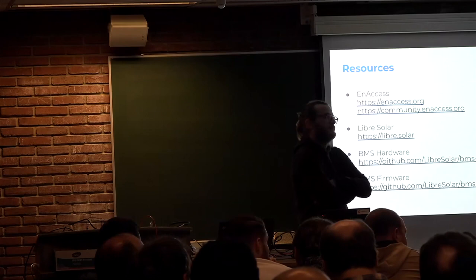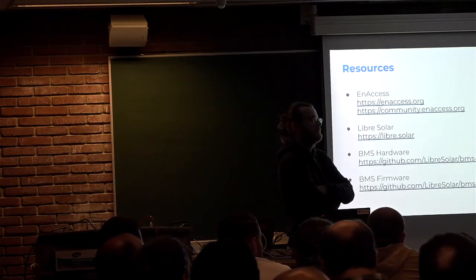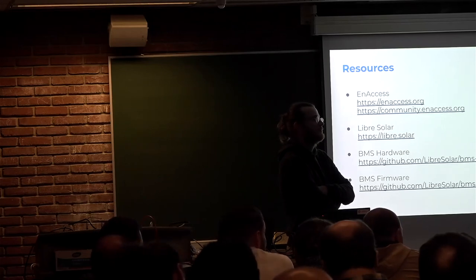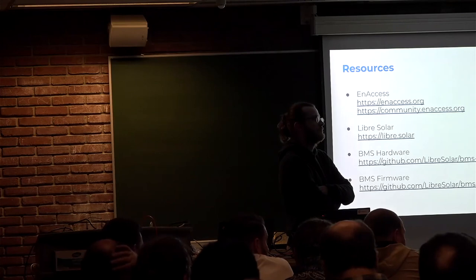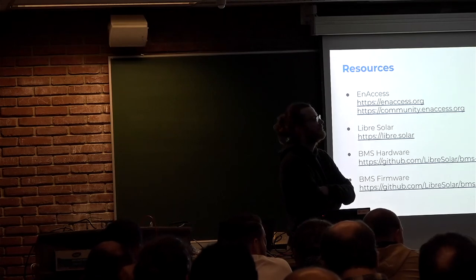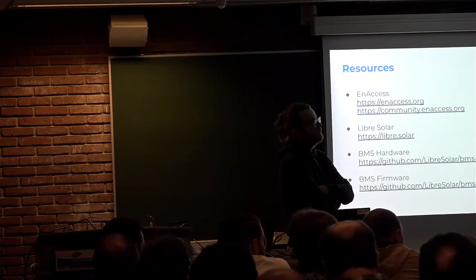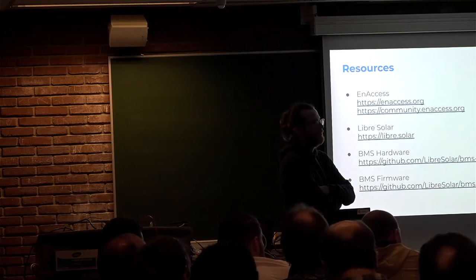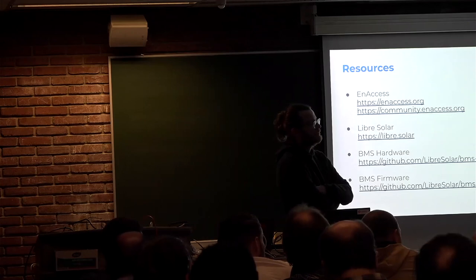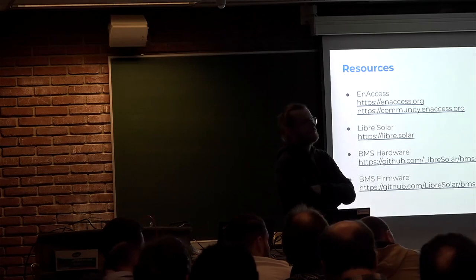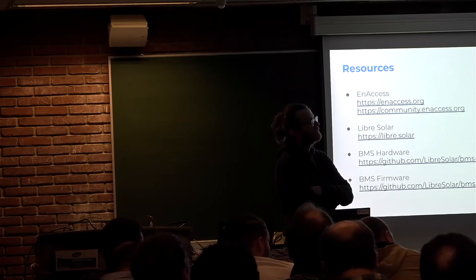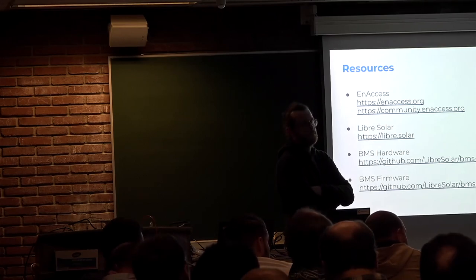Have you had cases where you needed to handle balancing between lithium cell storage and other kinds of storage, such as compressed air, concrete, or redox flow batteries? So far it has only been lithium cells of different chemistries — lithium iron phosphate and lithium nickel manganese cobalt oxide. We were in discussions with people developing redox flow batteries, where the voltage is smaller, so you could potentially monitor multiple cells at once and get an average. For the other storage technologies mentioned, we haven't tried, but if the voltage range matches, monitoring should be possible.